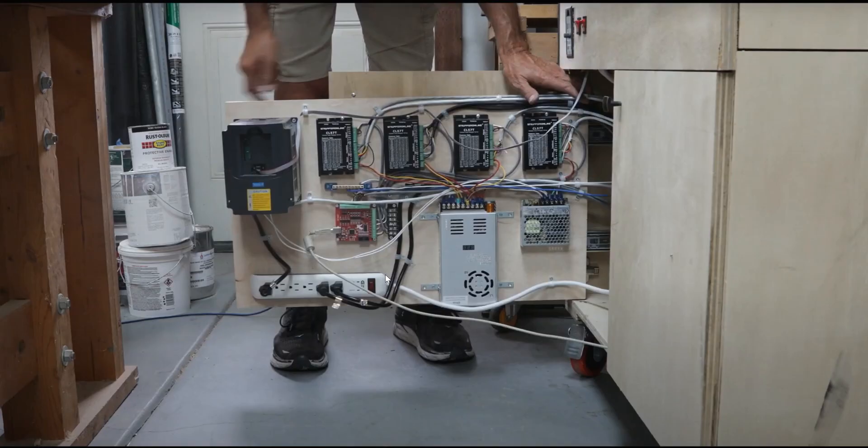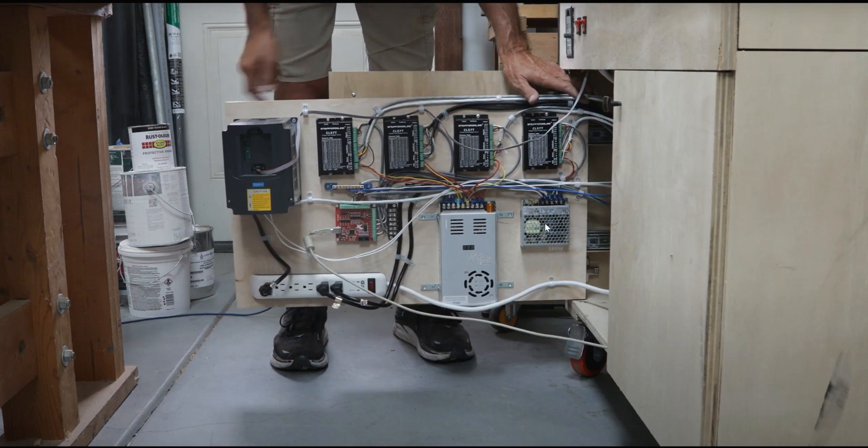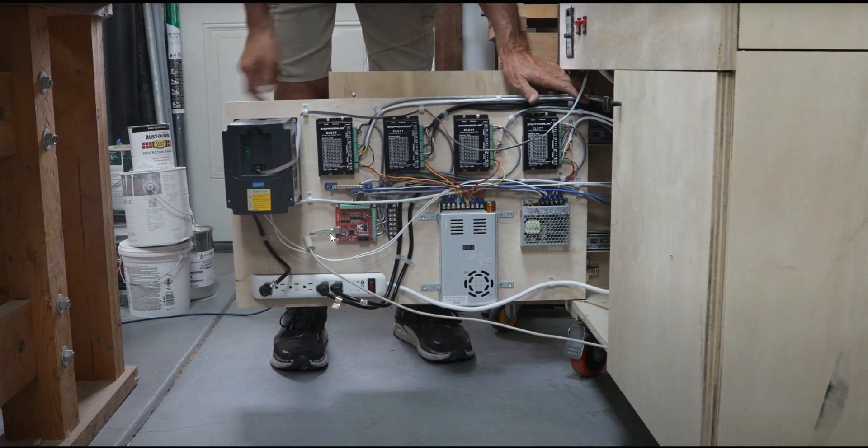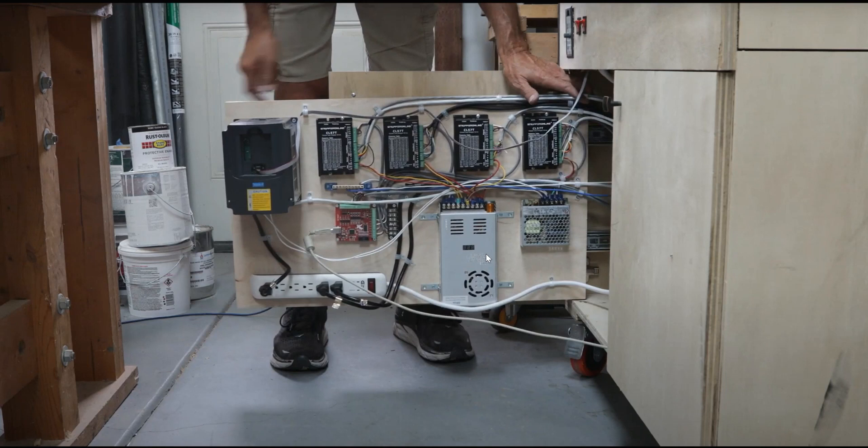On top of the fluctuation in power draw that's going to naturally affect all of his sensitive electronics. Now as we look here we do see a ground bar and I'm going to let him explain why he installed it, but we really need to discuss this more because we're seeing this done more and more in the CNC world. This stuff has all been covered before. CNC 10 years ago did not have the amount of resources we see today. When I see this being done it tells us that the end users are really not even researching the topic to the level they should. They're trying to make things simple for themselves and then they try to pass on the information. And unfortunately if you're a novice and you're trying to do this correctly, you see bad habits like this, dangerous habits more importantly, that can lead to utter devastation in catastrophic terms if of course a spark or a short circuit happens.